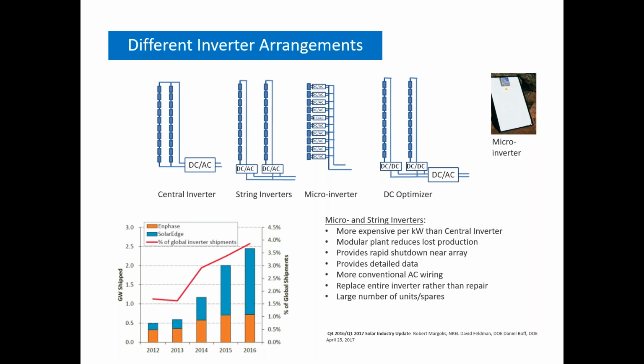So there's pros and cons with these. EPC contractors generally prefer central inverter because it's lowest initial cost. O&M contractors often prefer string inverters for several reasons. They're a modular plant which reduces lost production, and provides rapid shutdown near the array. The string inverters and microinverters can provide detailed data through some pretty sophisticated communications that they have available through those platforms. Most of the wiring downstream of where the inverters are located is conventional AC wiring.